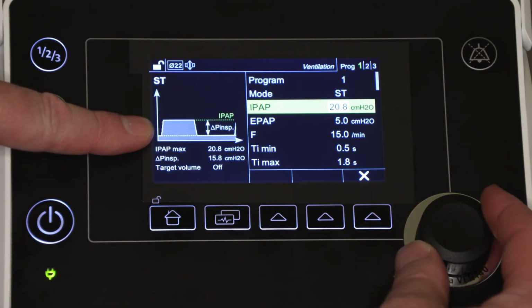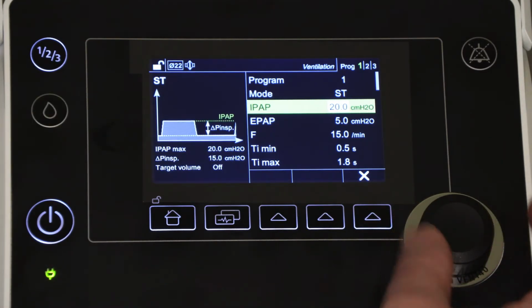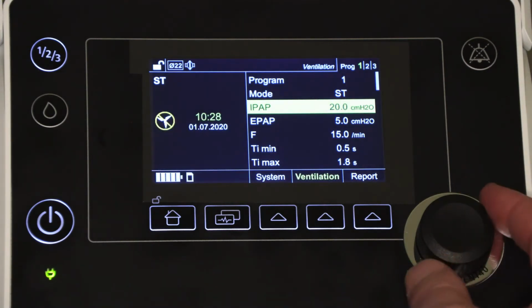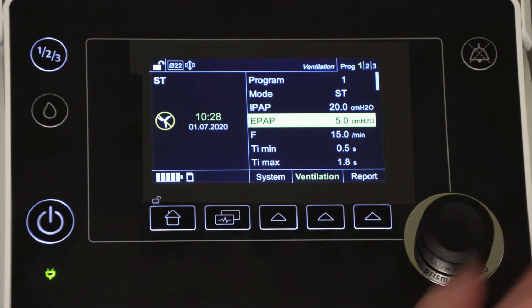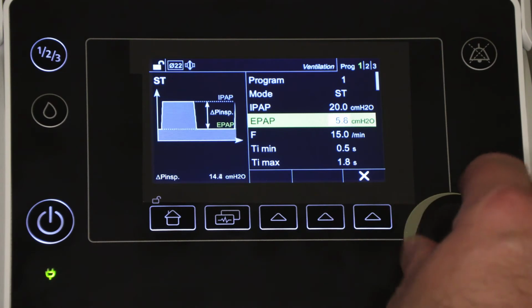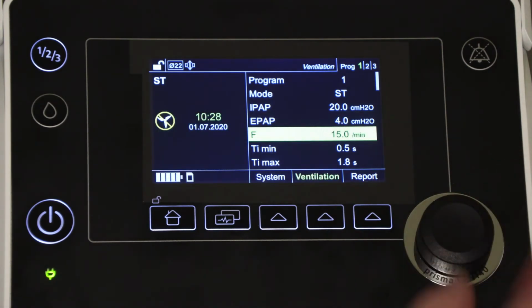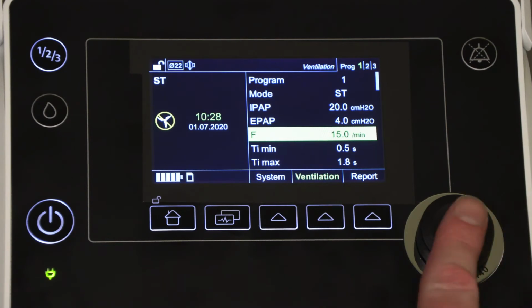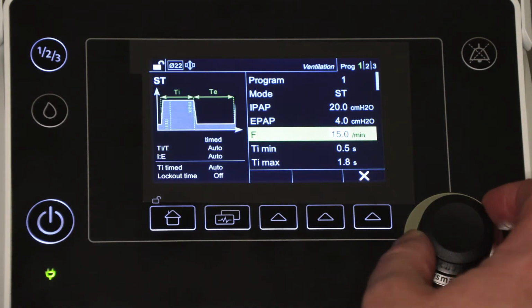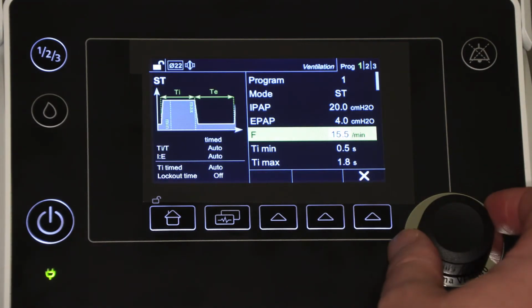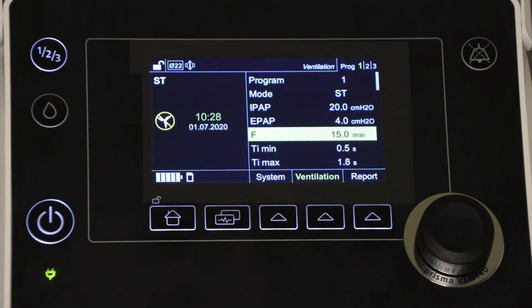The IPAP can be adjusted to anywhere between 4 and 40 centimeters with prismaVENT 40. The EPAP can be adjusted between 2 and 25 centimeters. F stands for frequency, meaning the frequency of backup breaths. So this is your backup rate, and it can be adjusted and set to a value anywhere between a frequency of 0 to 60 breaths per minute.